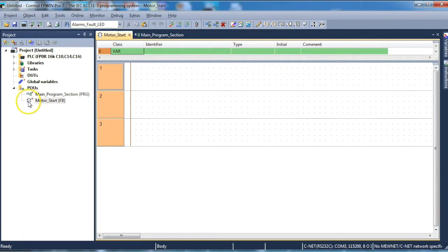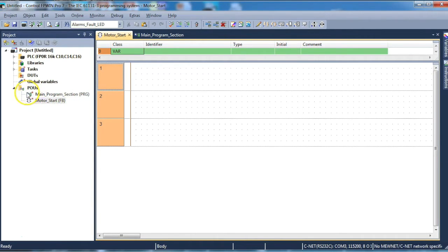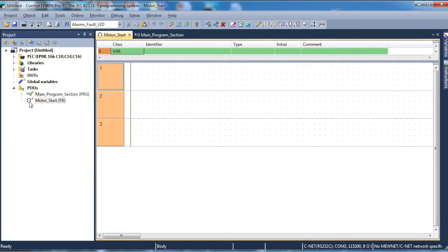Notice that the new function block has a slightly different symbol to our main program sections. This is to signify that the main program sections are scanned every time the PLC runs. But with regards to our user-defined function blocks, they are only scanned at the time they are called up within another main program section.